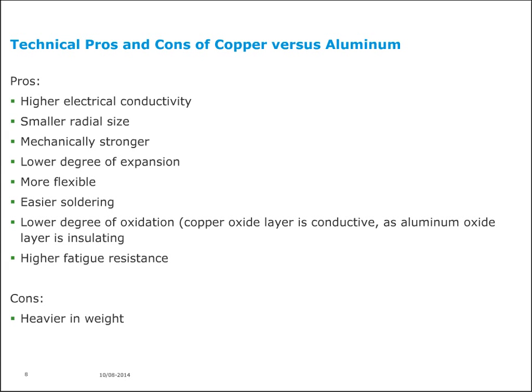Mechanically, it's stronger. It has a lower degree of expansion. It's more flexible, easier soldering, a lower degree of oxidation. Copper oxide layer is conductive, as aluminum oxide layer is insulating. This is a major difference. Copper is not oxidizing so quickly, but when there is an oxide layer, it has the same nature as the basic material. And finally, a higher fatigue resistance for copper compared to aluminum.